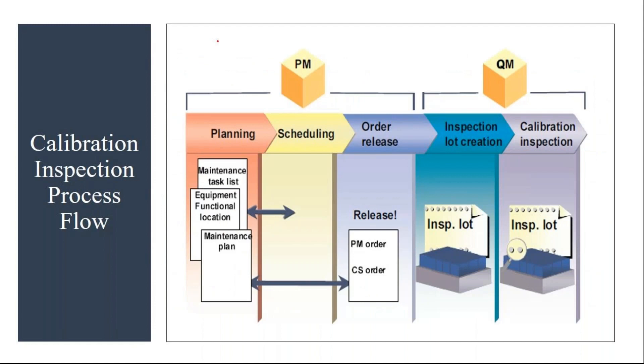From the PM side, they will do all the planning activity. They create test equipment, then they will create the maintenance plan. When they do the scheduling, the system will generate a calibration order. Along with that order, for QM, it will generate an inspection.